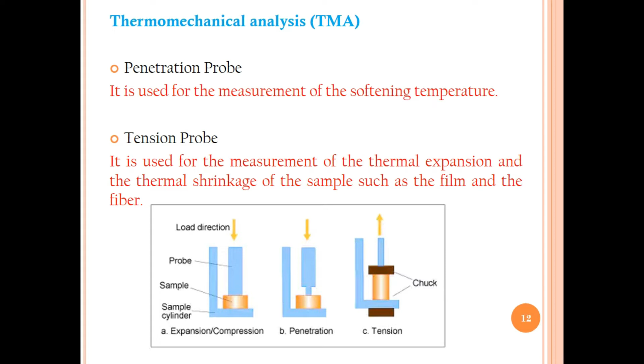Next is the tension probe. It is used for the measurement of thermal expansion and thermal shrinking of samples such as film and fiber. This is shown in figure C. There's the tension probe. The sample is placed between two cylinders that apply an up and down motion on the sample. This is called the tension probe. The probe depends upon the material under observation. What kind of probe we have to use in TMA analysis purely depends upon the nature of the sample under observation.